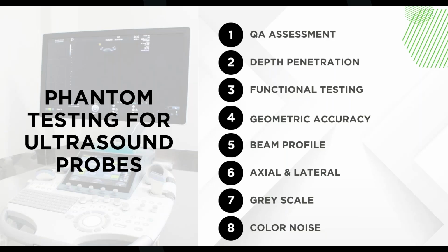All right. Is anybody familiar with the ultrasound phantom at all? All right. So this is our ultrasound phantom that we use. On here you have wire dots that are all measured on here. This particular one tells you whether it's 10 millimeters or 1 centimeter difference. You also have these anechoic structures that you can hit here on the right hand side, and then you have a grayscale as well on this particular phantom.